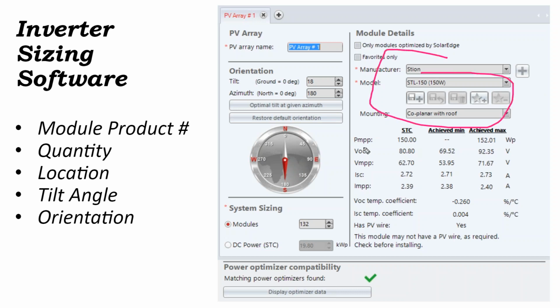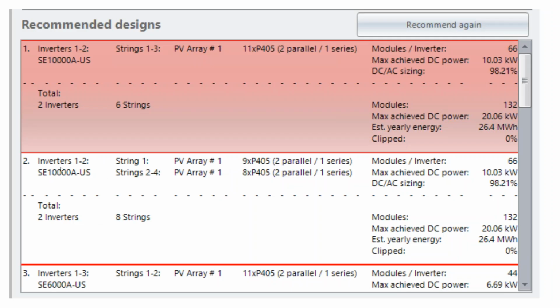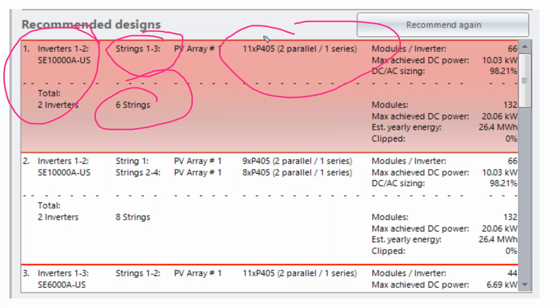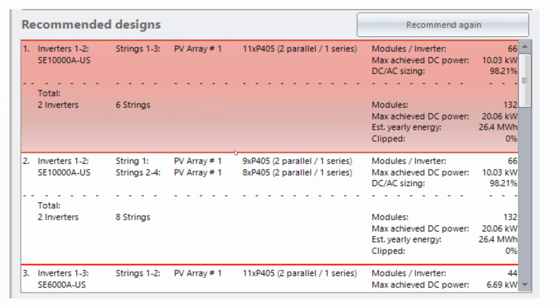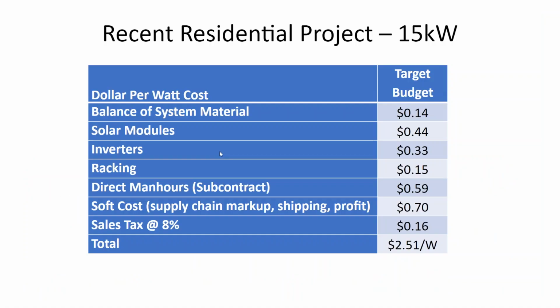You're entering the panel you're using. You're putting in how many solar panels you're using. You're putting in the array tilt and orientation and location. And then it just spits out, okay, you're going to use this 10 kilowatt inverter, and each inverter is going to have 3 circuits, and that'll be 6 circuits total. And it's recommending what optimizer to use. Basically, your manufacturer design tools will tell you how many modules are going to go on a circuit, what optimizers are compatible with your solar panels, and what microinverters are compatible with your solar panels.